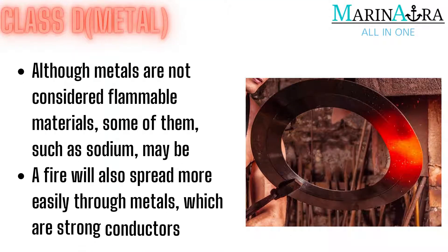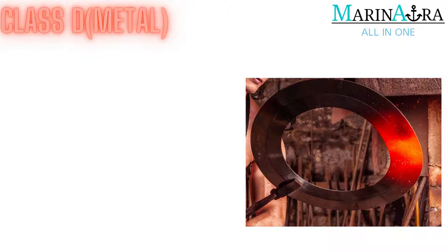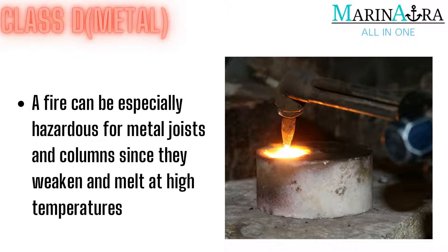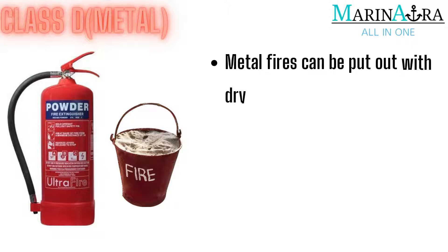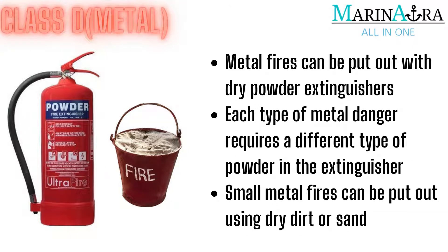Class D — Metal. Metals are not commonly thought of as flammable materials; however, some metals, such as sodium, may be. Metals are also strong conductors, which aid in the propagation of a fire. At high temperatures, all metals weaken and melt, which may be a major issue when metal joists and columns are used as structural parts in a fire. Water may actually function as an accelerant in metal fires, so how would you handle one? Metal fires can be put out with dry powder extinguishers. Depending on the type of metal involved, the powder within the extinguisher may differ. Dry dirt or sand can be used to suppress small metal fires.